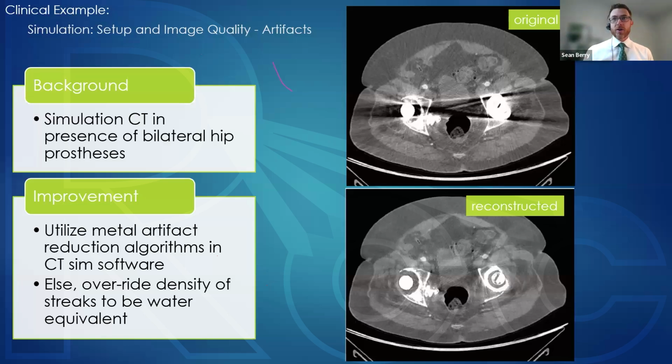We were going to talk about it a little bit later, but you also need to make sure that your CT to density curve is encompassing that material as well. But even then, and even with better dose calcs like Acuros, which is the Boltzmann solver, or EMC, we still let our physicians know that there is a little bit more uncertainty in that than what we would normally see.